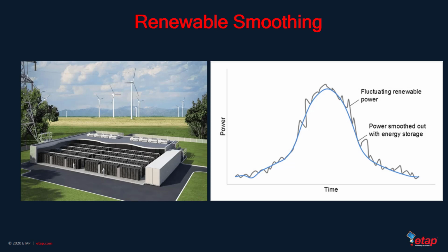So therefore, one way to reduce these effects is to smooth out the power production using energy storage systems. The use of energy storage technology has the potential to be far faster than regulation by gas or steam turbines. This fast response time can minimize momentary electricity interruptions, which are more costly than sustained interruptions. These storage technologies can vary output rapidly, changing from no output to full output within seconds.